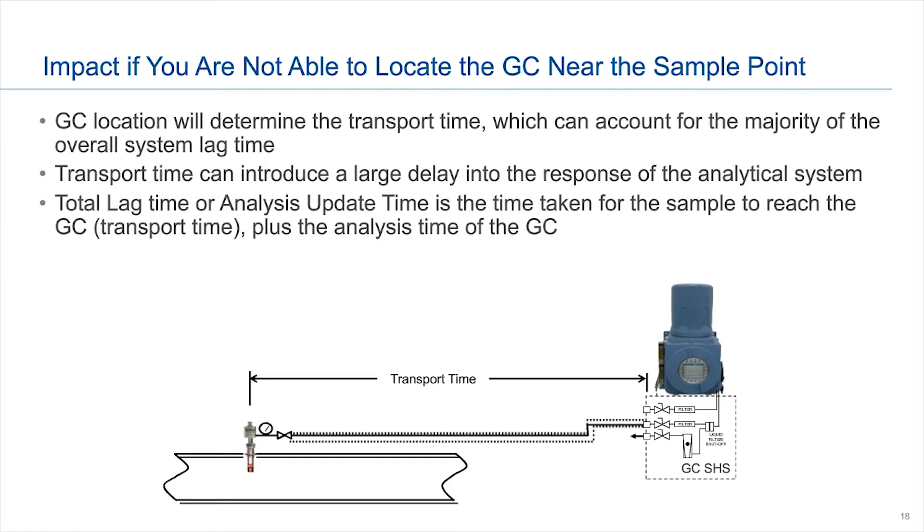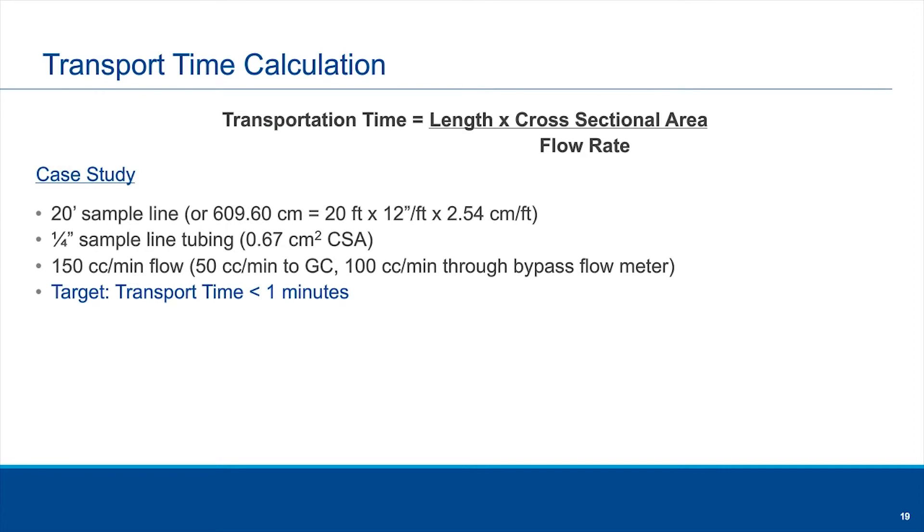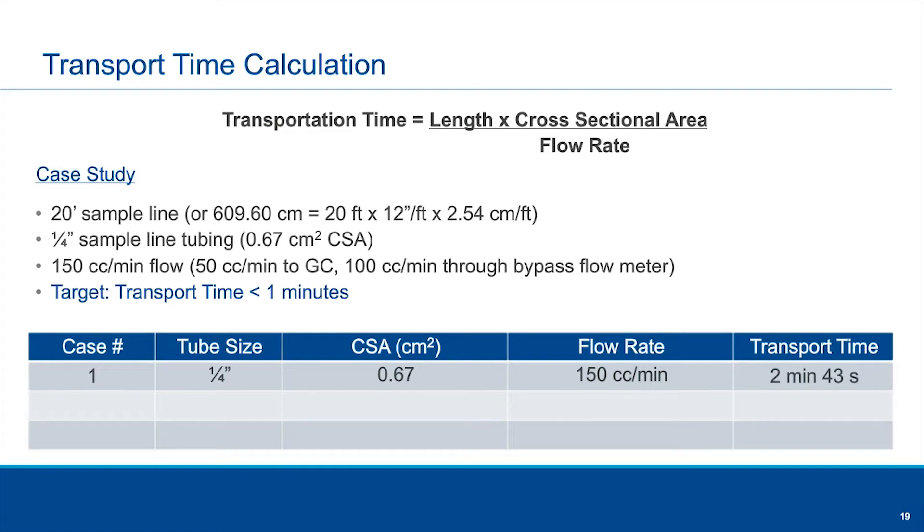You can see the impact of distance on your sample time from this little formula: it's the length of your pipe times the cross-sectional area of your tubing, divided by the flow rate. Looking at a typical case example: say your pipeline is about 20 feet away from your sample point — pretty close for some applications, especially with a full shelter. We went with traditional quarter-inch sample line tubing and a flow rate of about 150 cc per minute — the combination of flow to the GC plus flow through the bypass meter. In this case, our target was to get a transportation time to the GC of less than one minute. When we work out the math from the given information, it would take almost two to three minutes just for transportation, plus whatever your sample analysis time is for your total update time. That's pretty long, especially if you need a quick feedback loop.